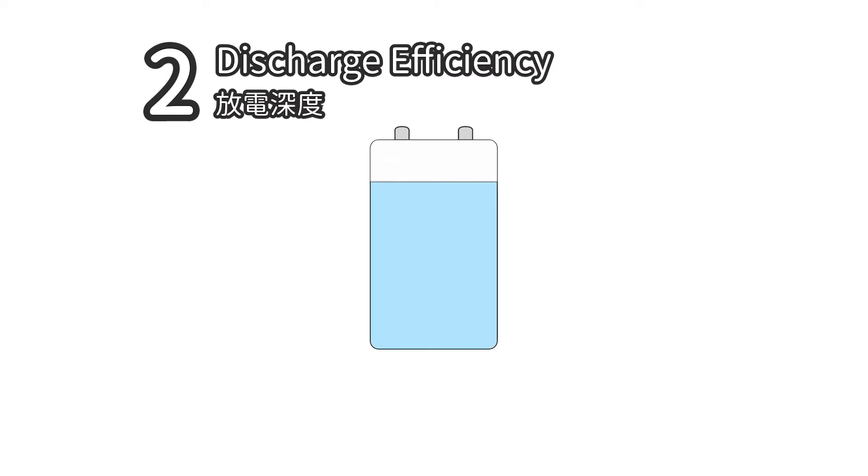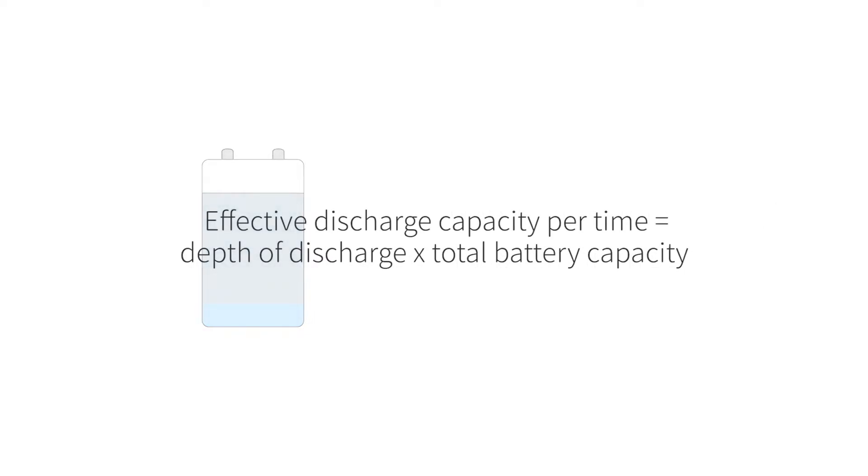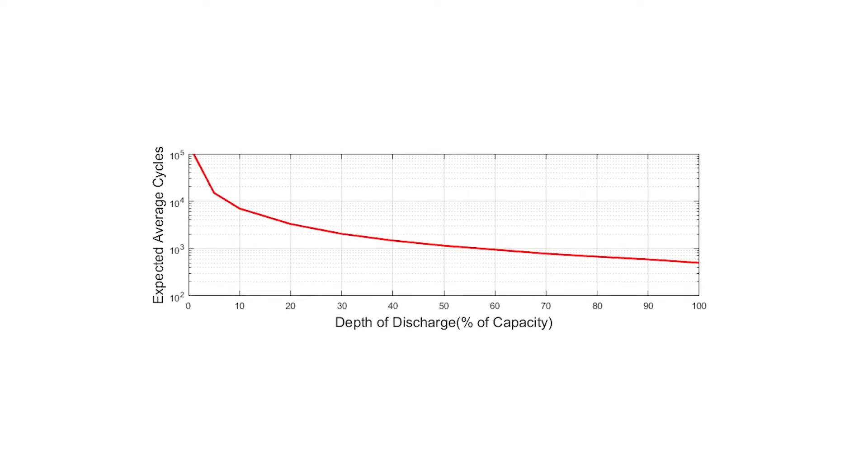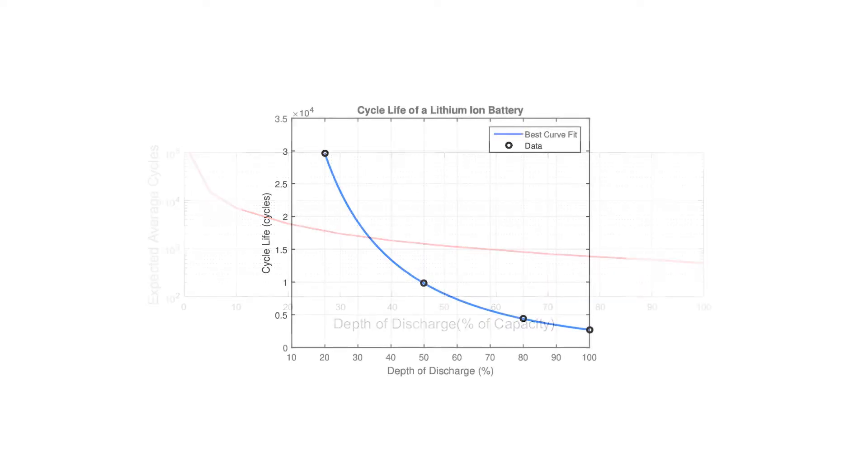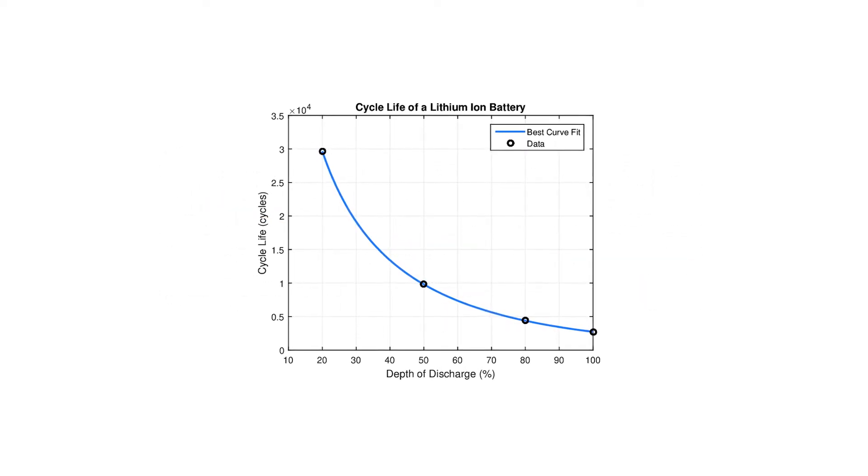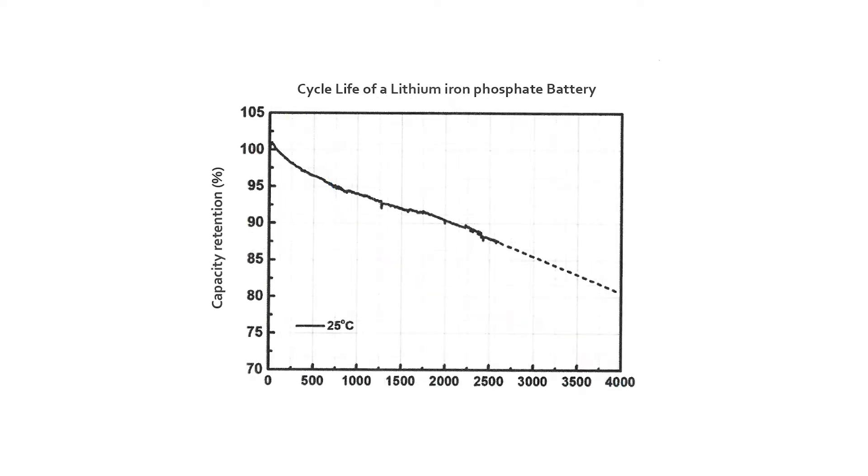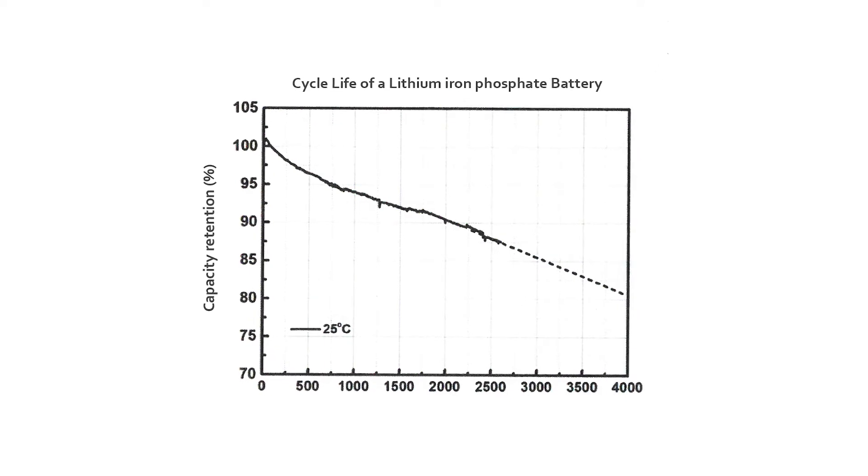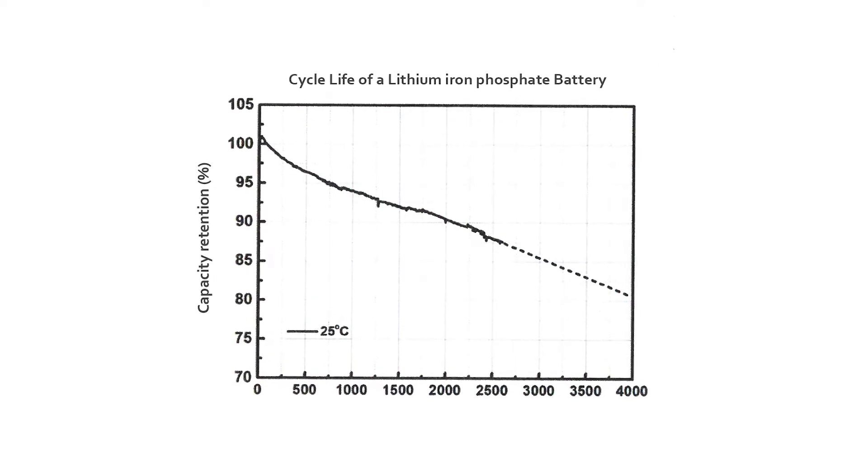2. Depth of discharge. The depth of discharge is 90%, and the remaining state of charge is 10%. Power per effective discharge equals depth of discharge times total battery capacity. Lead-acid batteries have a depth of discharge of 50%. To put it simply, lead-acid batteries are only half usable. 90% depth of discharge for lithium-ion batteries. That is, 90% can be used. The lithium iron phosphate battery has a depth of discharge of 95%. That is, 95% can be used.